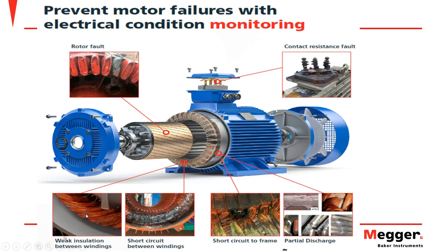And what I'll do is that will just deteriorate very quickly. So if we're going to be testing at a certain voltage and then it starts to carbonize, then as we start increasing that voltage from 0 volts, the dielectric strength between the turns will deteriorate with the amount of carbonation and arcing as time goes by, enabling us to be able to predict, okay, it's starting to have unbalance across the three phases because we've noticed that the sine wave is starting to deteriorate at maybe 1600 volts.